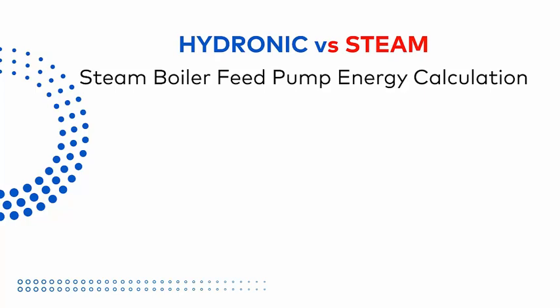It's also very important to remember that since we're using Maxi-Therm vertical flooded heat exchangers in our system and we'll be bringing the full 100-pound steam pressure to those units, there will be plenty of pressure to push the condensate back to the boiler feed unit without pumping it. So the only pumps we need for our system are the boiler feed pumps.